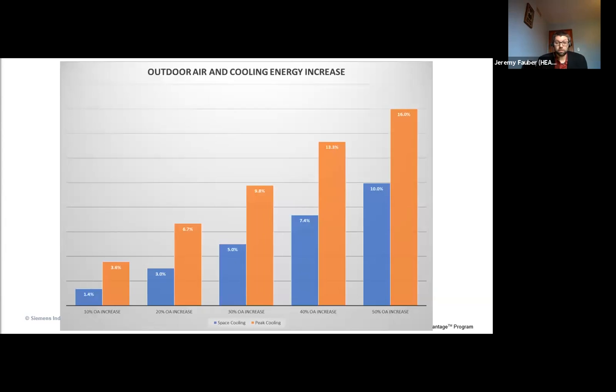On the next slide, I'm going to be talking about increases over that baseline. So a 50% increase is taking that from 24% outside air to 36% outside air. It is not to a 50% outside air total, which would be about 100% increase. Another element that's going to be with this is your equipment efficiency will impact your energy usage a little bit. Less efficient, you're going to use more energy. More efficient, you're going to use less energy.